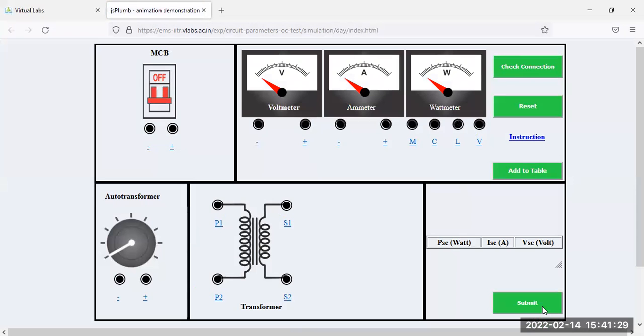Yeah, for this short circuit test, again the same things you have to follow here. That means you only have to be concerned about the connection of the measuring instruments towards the HV side and LV side to short it. Okay. So start from the MCB. The positive terminal of this MCB is connected to the auto transformer positive terminal. So from this point to this point. Okay. And the negative polarity of the MCB is connected to the auto transformer negative polarity.